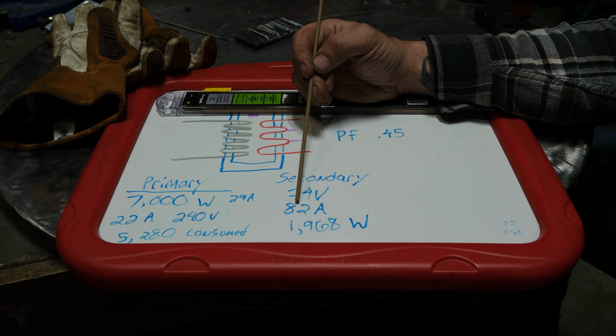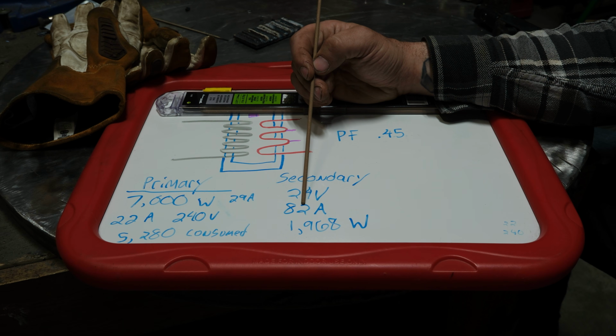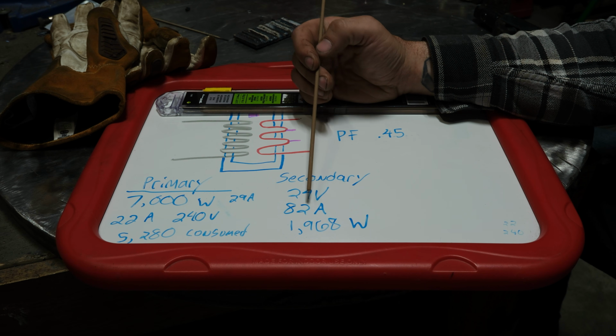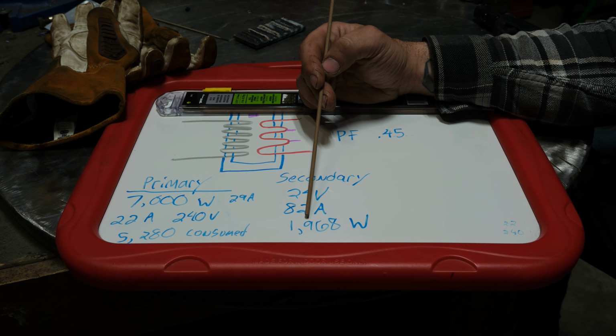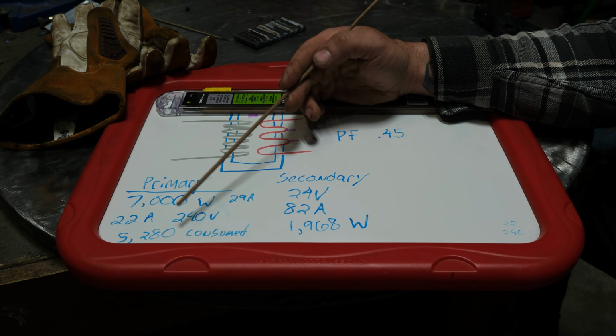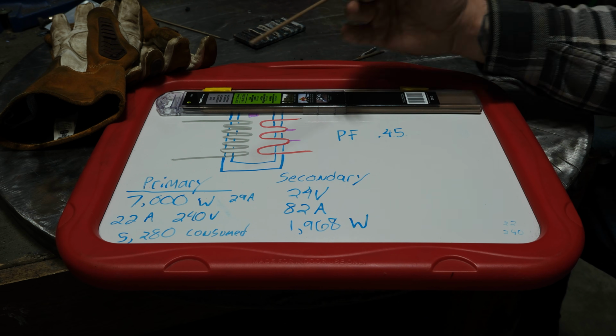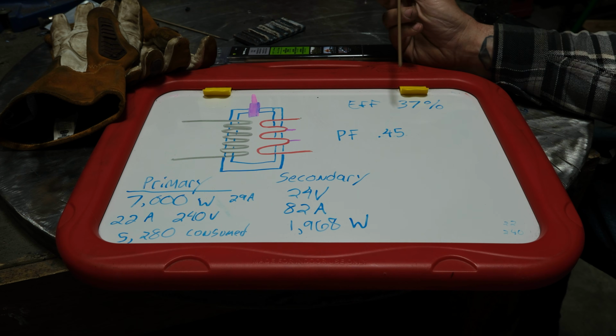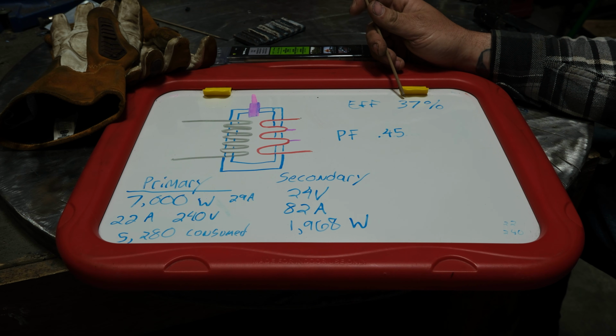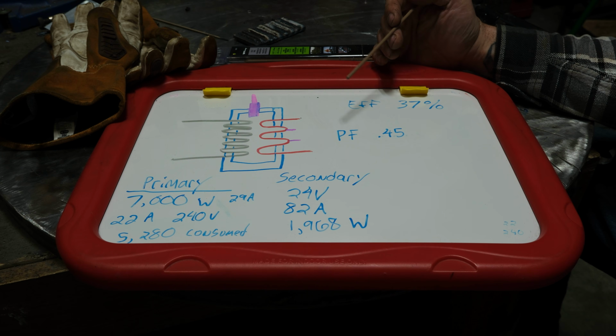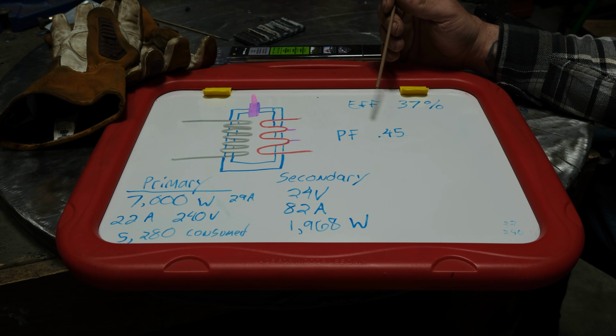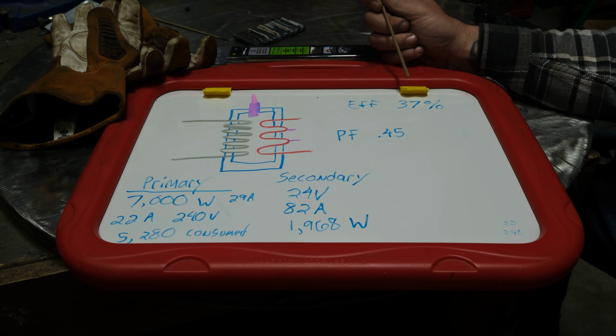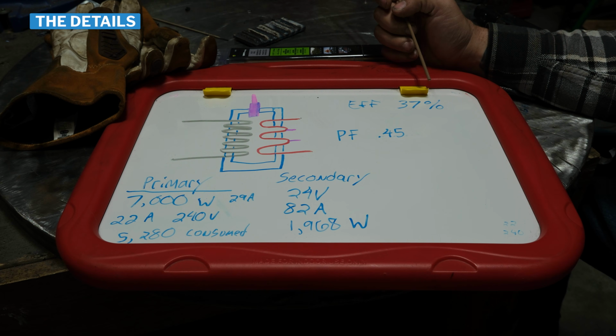So let's just say somewhere between 70 and 82 amps is what it was outputting. At 82 amps, 24 volts, the output of the machine was 1,968 watts, which isn't a whole lot given the input power. In simple terms, the efficiency of this device is basically 37%, meaning at this output, somewhere between 75 and 85 actual amps, it's only 37% efficient at turning input power into output power, probably the worst I've ever seen on a welder.